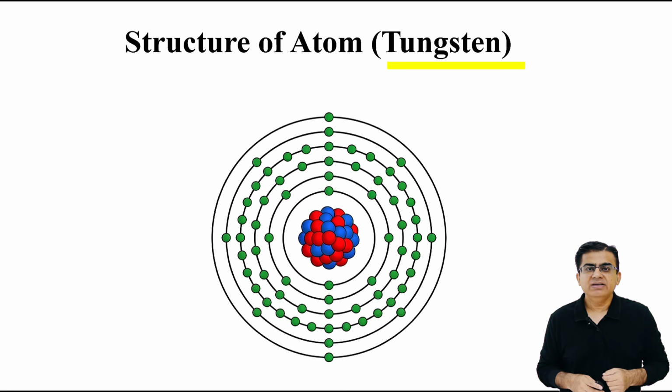First, tungsten has a very high atomic number of 74. Having this high atomic number is absolutely essential. High atomic number means a larger nucleus. A larger nucleus means more positive protons. A larger nucleus with more positive protons creates a much stronger attractive braking force for the incoming electrons. This massive braking force dramatically increases the overall efficiency of our Bremsstrahlung radiation production.